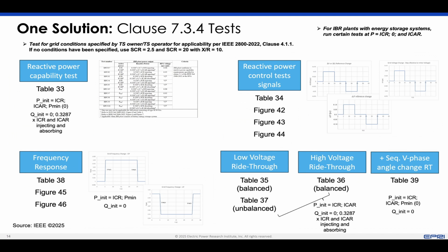And IEEE 2800 in clause 4.1.1 recommends that the transmission entity provides numbers, but if they don't provide these numbers or conditions, then 2800.2 suggests to run these tests once at a strong grid with SCR 20, and then at a weaker grid condition with SCR 2.5. Now, these are arbitrary numbers, and therefore you can adjust those numbers when you engage in conversations with the transmission entity. Also, to point out is that these tests shall be run for various levels of active power prior to the disturbance.